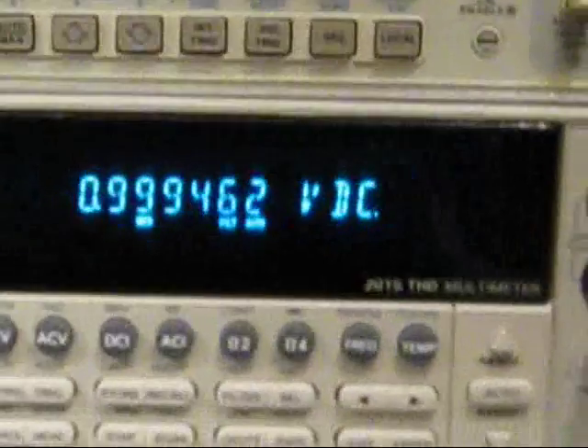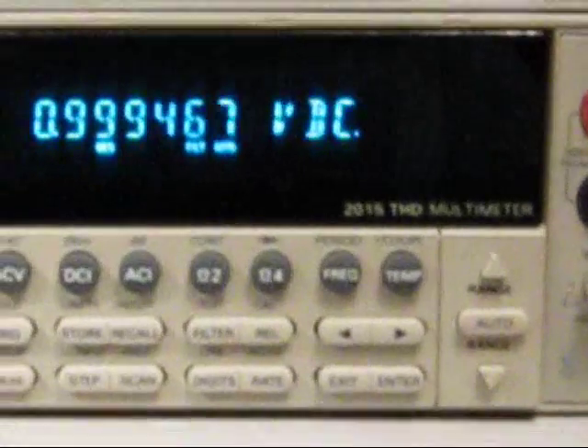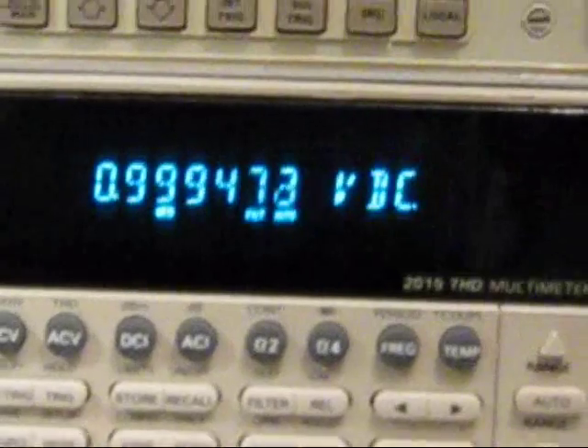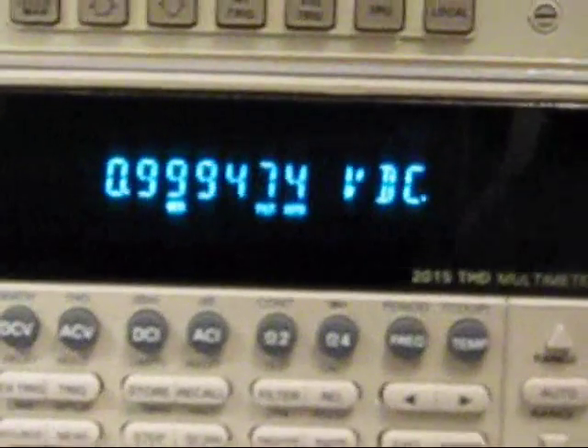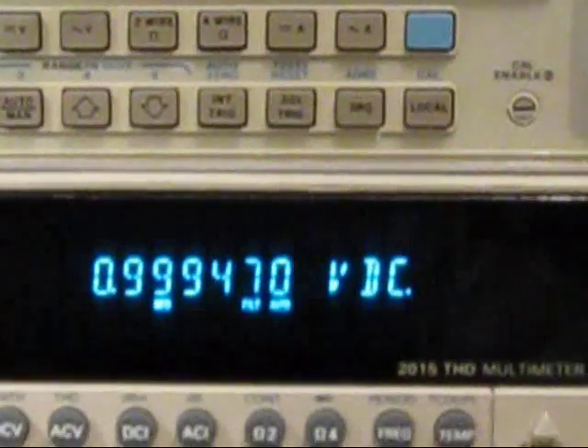So we've set the calibrator up to give us one volt of DC. And if we look at what we've got on the meters at the moment, we can see the Keithley showing 0.99947.